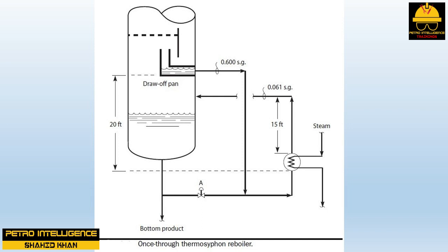Common symptoms of loss of once-through thermosyphon circulation include: inability to achieve normal reboiler duty, low reflux drum level accompanied by low tower pressure even at a low reflux rate, bottoms product too light, reboiler outlet temperature hotter than the tower bottom temperature, and opening the steam or hot oil inlet heat supply valve does not seem to get more heat into the tower.